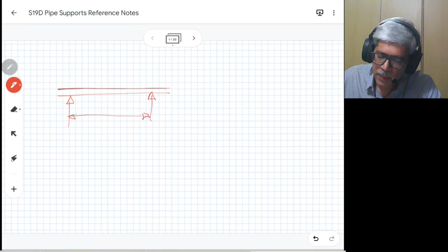Let's say we are having a pipeline of certain size in which the code recommends a length L for a straight pipeline. And if your pipeline is such that you are having a bend in that pipeline, and this is a horizontal pipeline, so we are looking from the top at this pipeline, and if you want to decide how much should be the span for supporting this pipeline, the guideline is that the span between the supports for such a pipeline should be 25% less than the L. So the span here, L1, will be equal to 0.75 L, 25% less.